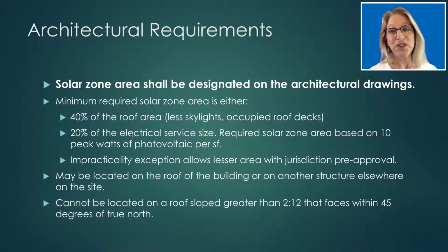So let's go through the various requirements in this provision by discipline. The architect is responsible for the following details. They need to show the solar zone area. It needs to be designated on the architectural drawings. And the minimum required solar zone area is either 40% of the total roof area, less any areas for skylights and any occupied roof decks, or it can be 20% of the electrical service size.